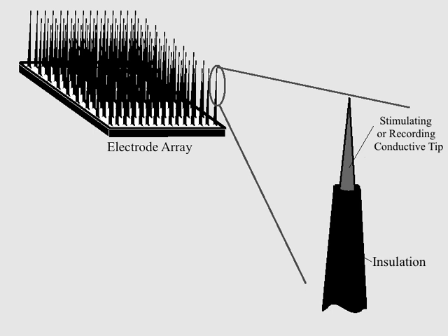Corrosion is a major issue with neural electrodes. Corrosion can occur because electrode metals are placed in an electrolytic solution, where the presence of current can either increase the rate of corrosion mechanisms or overcome limiting activation energies. Redox reactions are a mechanism of corrosion that can lead to dissolution of ions from the electrode surface. There is a base level of metal ions in tissue; however, when these levels increase beyond threshold values, the ions become toxic and can cause severe health problems. In addition, the fidelity of the electrode system can be compromised.